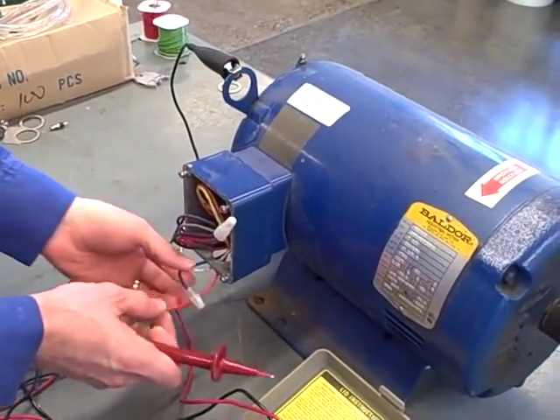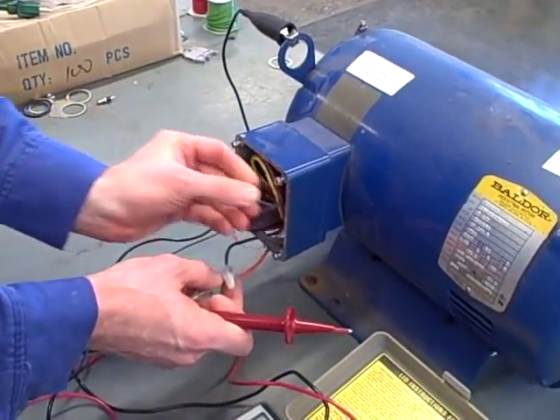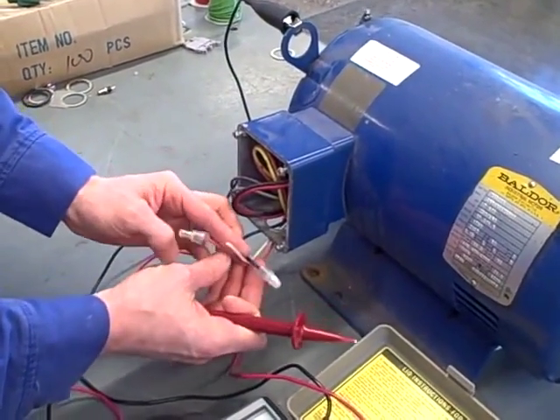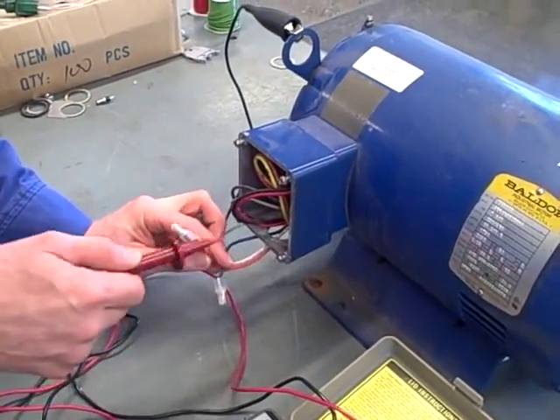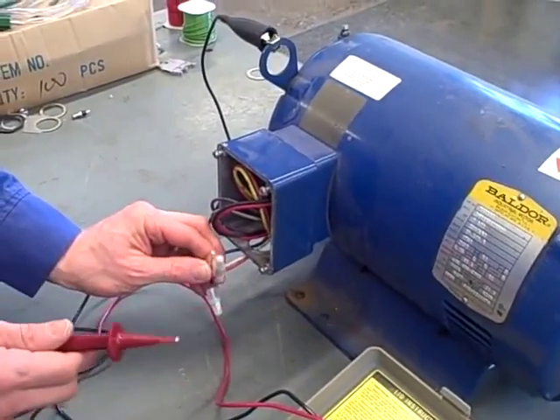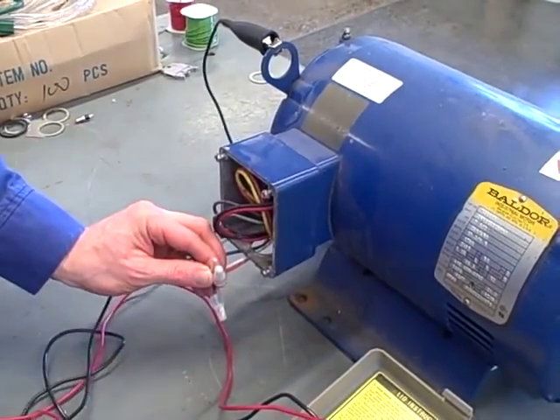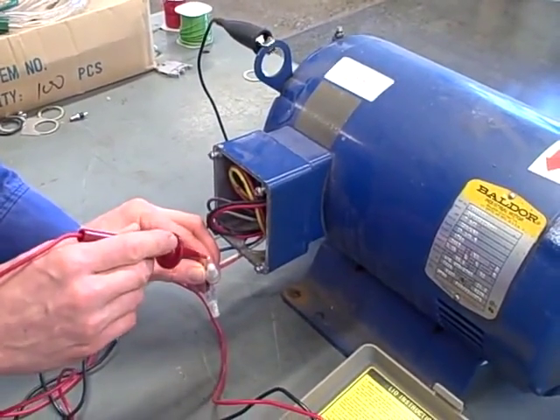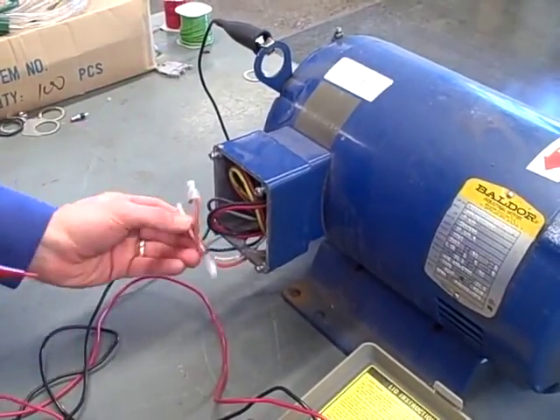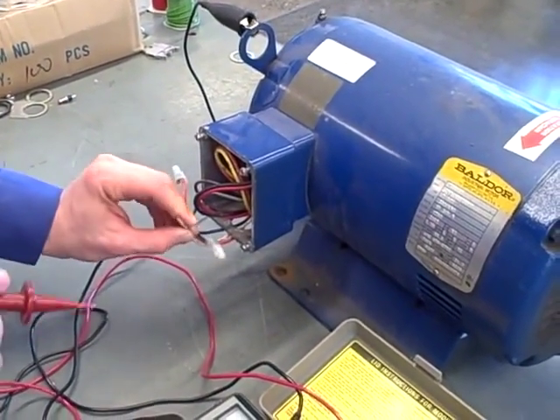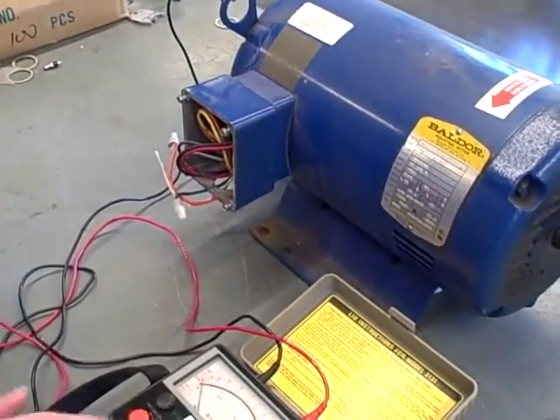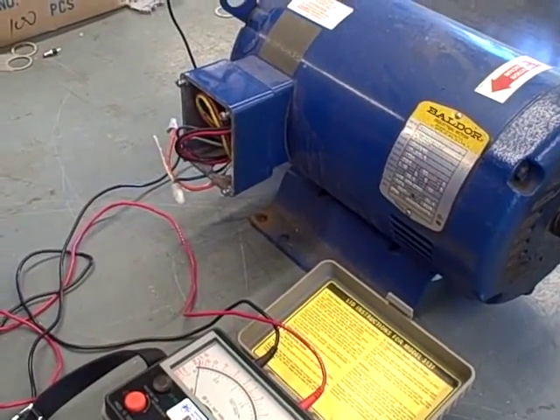Next, I'm going to take a look at my three-phase windings right here coming out of the junction box on the motor. I've got a blue, an orange, and a white, and I'm going to measure continuity with my insulation tester between these phases and ground. I have to be safety conscious here because this does put out a fairly high voltage when it does the test.